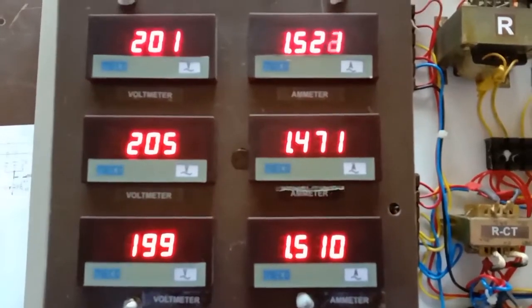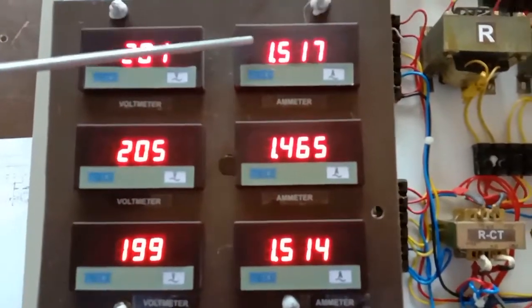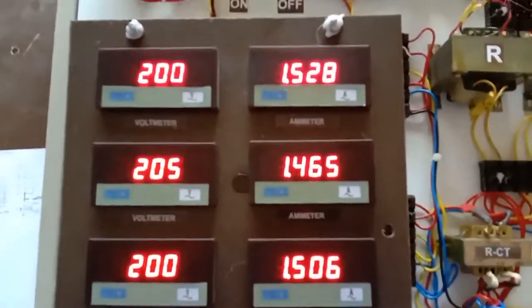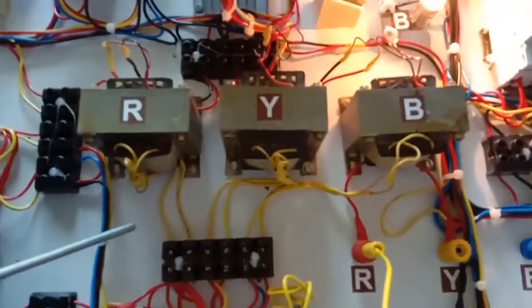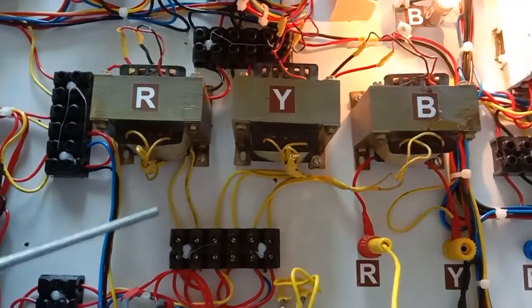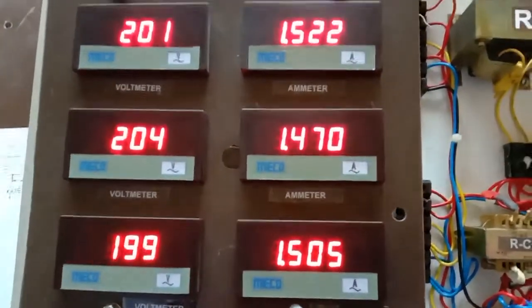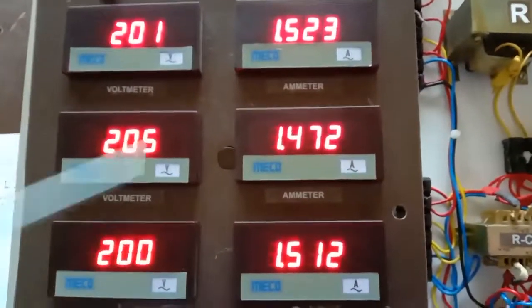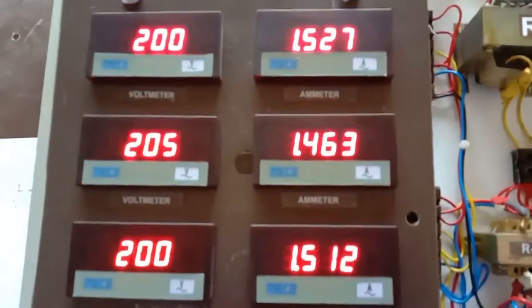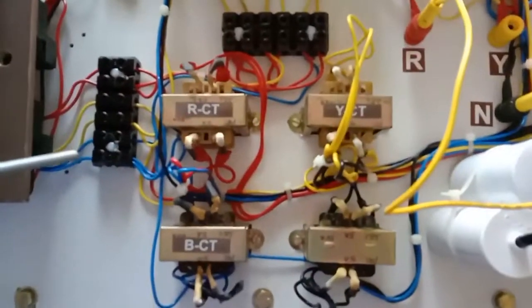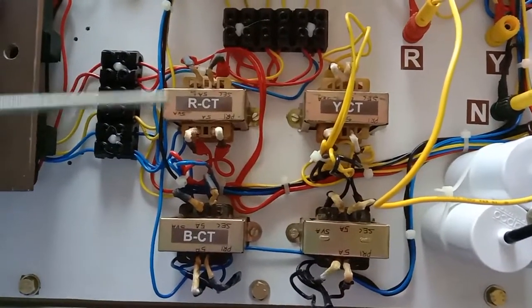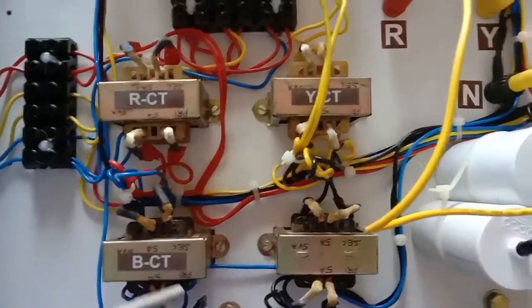this terminal block, and from this terminal block we have connected the three voltmeters, which give the voltages, and ammeters also, these three ammeters. So from the transformer secondary delta side, supply is given to the current transformers. From the transformer secondary, the supply is given to these three ammeters. In series with the ammeters, the supply is connected to these three current transformers, R phase, Y phase, B phase current transformers.